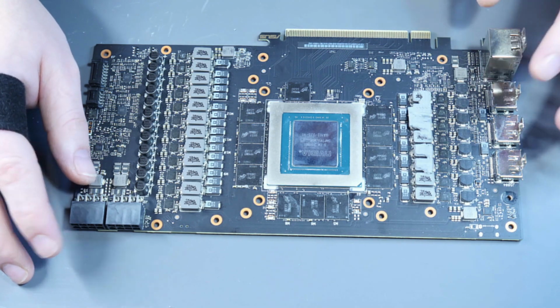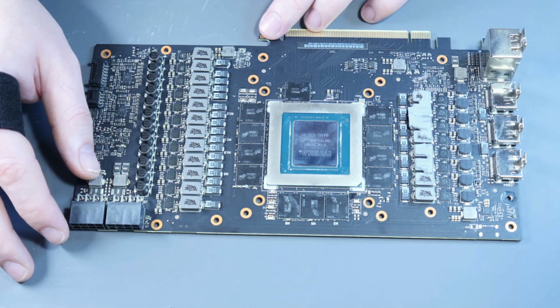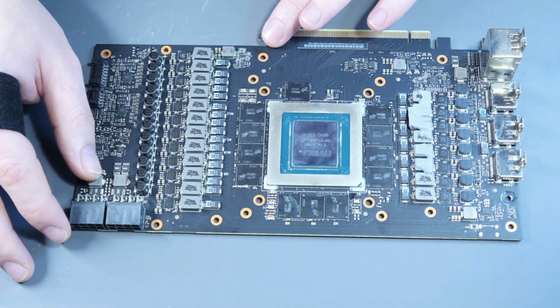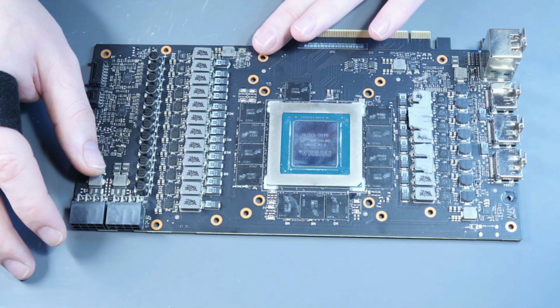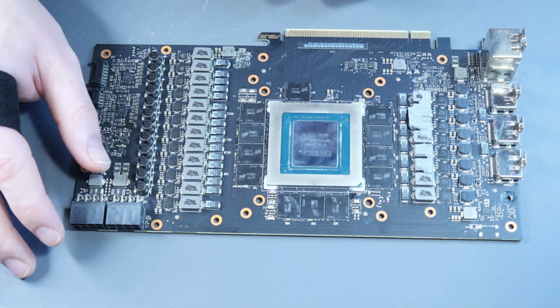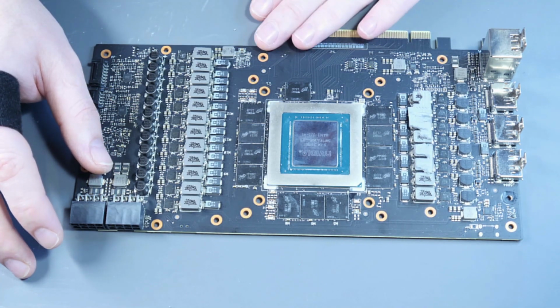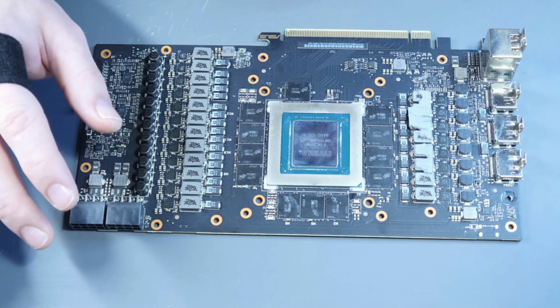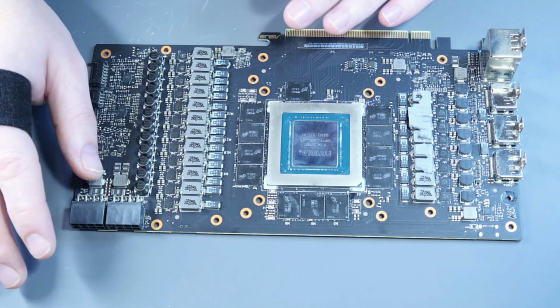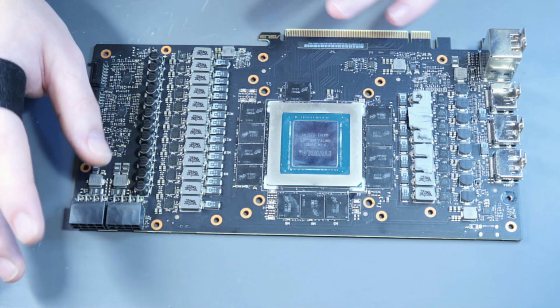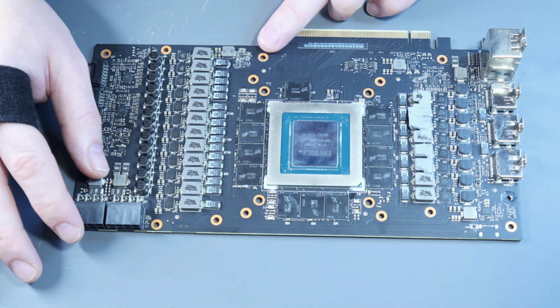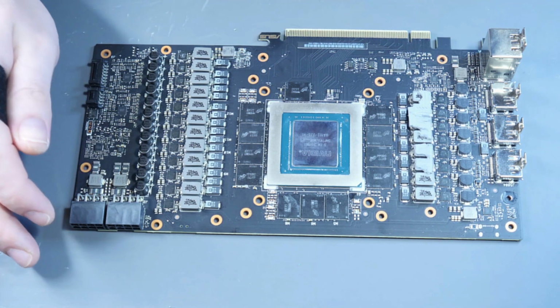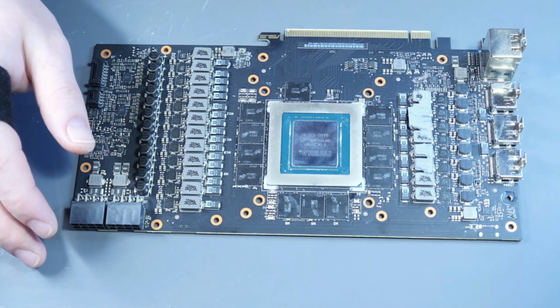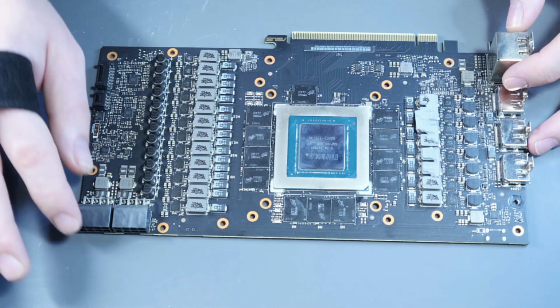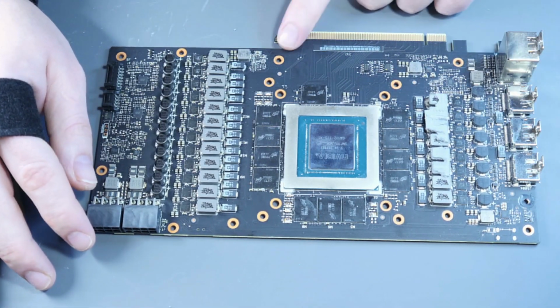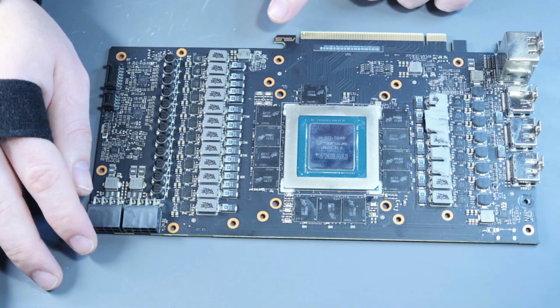So at this point in time, we are considering just touching this crack with a grinder, just to see the traces running through there, and see if we have any damaged traces. We don't have a schematic for this card, and we don't have a trace view for this card. So at this point, we're working a little blind, but we want to target the physical damage and see if we can reconnect whatever damage has happened there. The crack is very, very small. And we'll actually put it under the microscope now for you to have a look, and you can see what we're looking at.